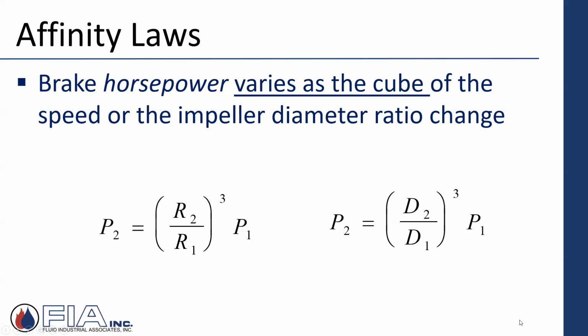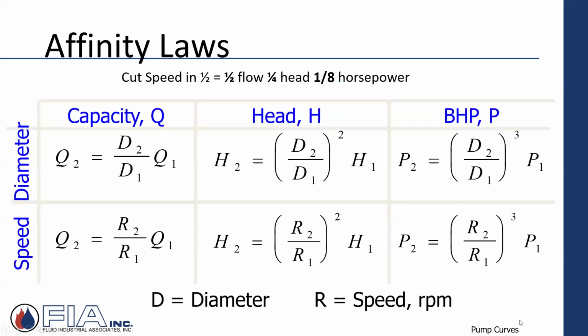And maybe they're not ready to replace the pump yet, but they can add a drive to that, and the utilities will provide these incentives. So they see the value, they know the value. So in this case here, it's saying it's a cubed relationship. But I change the speed from one to the other, whatever that difference is, cubed, not squared, but cubed times the original required horsepower. So there's where my pretty substantial energy savings can occur.